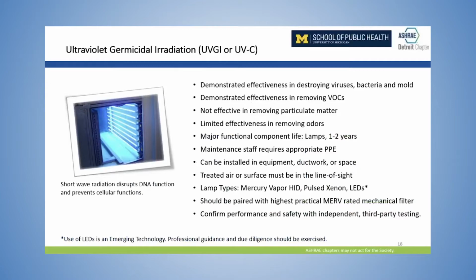So Stuart was talking about filters, and mechanical filters are just a real excellent strategy for providing, or part of the strategy for providing, good indoor air quality. But there are times, like now, when we want to do more, when we want to go beyond the ability of a typical mechanical filter. And so you may want to include an advanced air cleaning technology, either inside your major equipment, like your air handler or your ductwork, or standalone equipment inside specific rooms. You might look at incorporating something like ultraviolet germicidal irradiation, also known as UVGI or UVC or GUV or just UV.